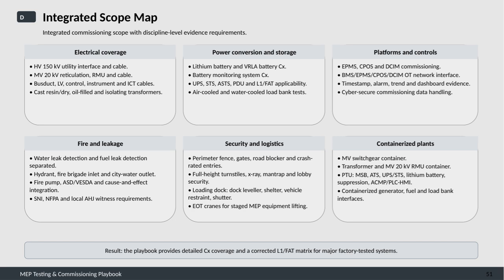For fire and leakage systems, the scope distinguishes between water and fuel leak detection. It covers fire hydrants, brigade inlets, city water outlets, fire pumps, and advanced smoke detection and suppression technologies, all integrated with cause and effect logic. Additionally, compliance with standards like SNI, NFPA, and local authority having jurisdiction witness requirements is emphasized.